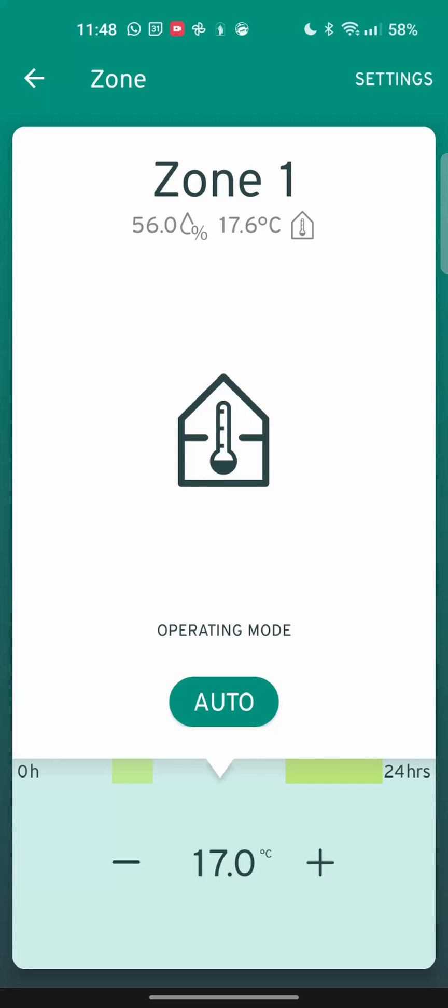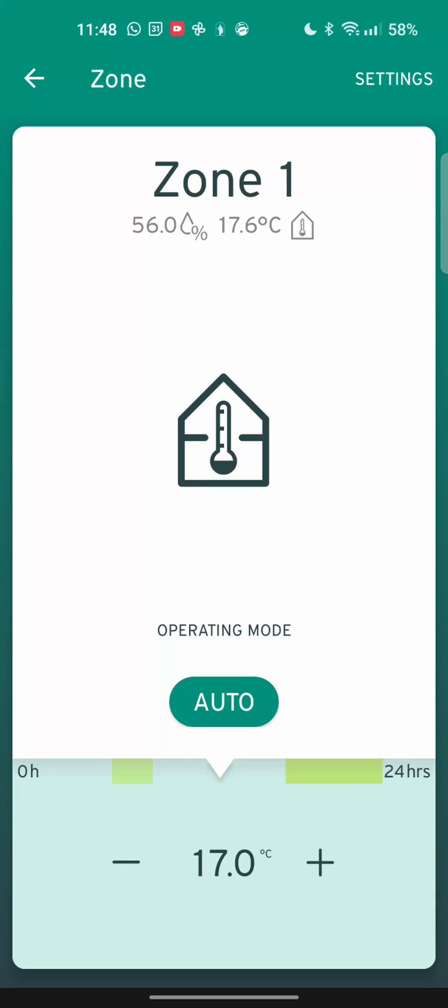Right now, you can see up the top there, zone one. Left-hand figure, it's showing me the humidity by that controller, Senso comfort controller. Right-hand figure is the interior, internal room temperature at the moment. Because I'm on my setback, I've got that down at 17 degrees, so the house still is above where it's targeting. But because I have it on full weather compensation, it's not really paying any attention. It will just keep sending the hot water around my radiators as needed and as per the weather compensation curve.